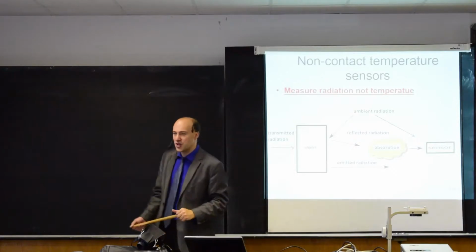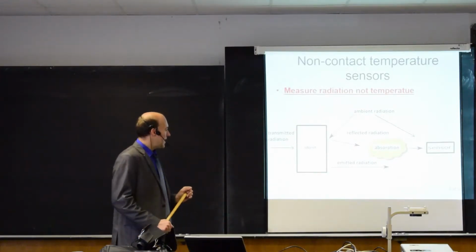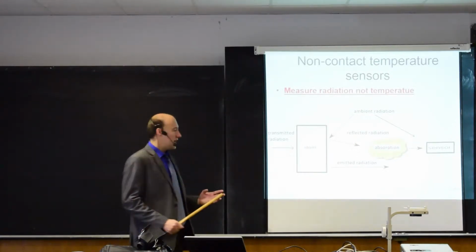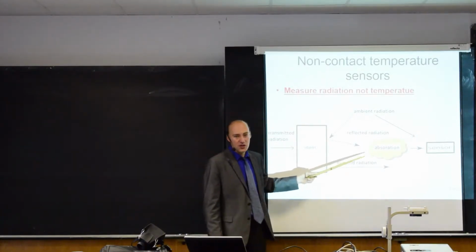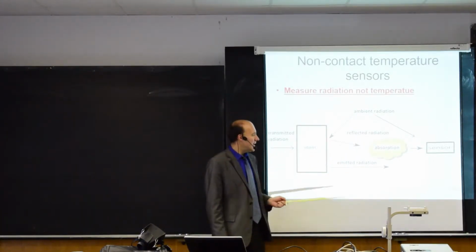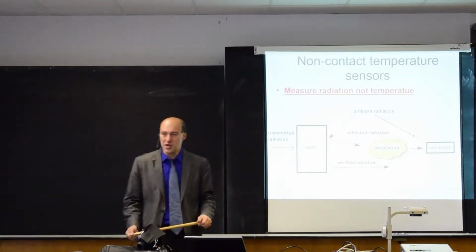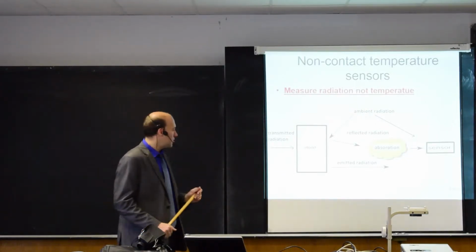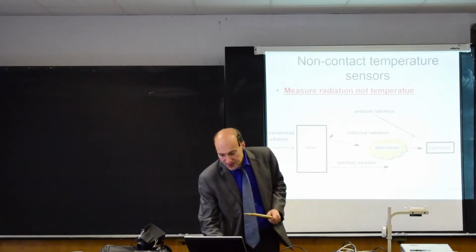This is absorption in the atmosphere, and it's quite important, especially if you measure over long distances. So if this distance is 10, 20, 100 meters or above, you may get some portion of the infrared radiation absorbed in the atmosphere. We'll see also some charts that relate this further.